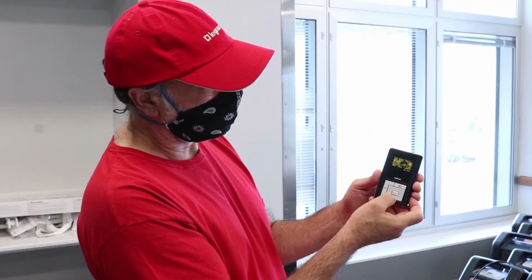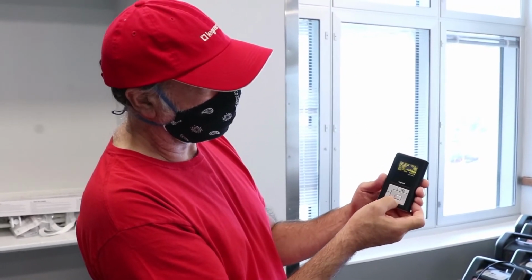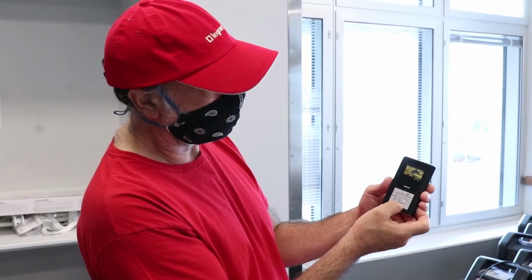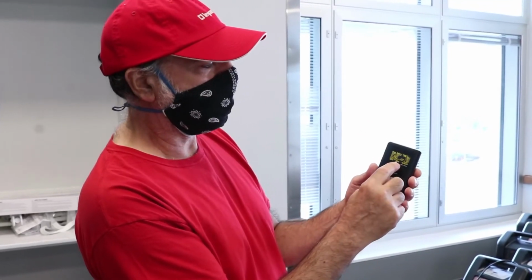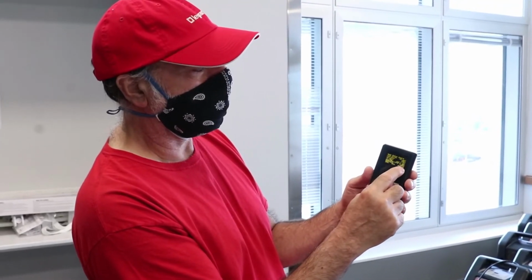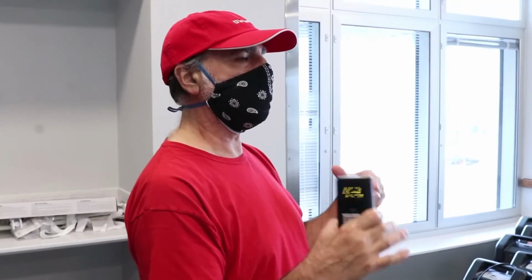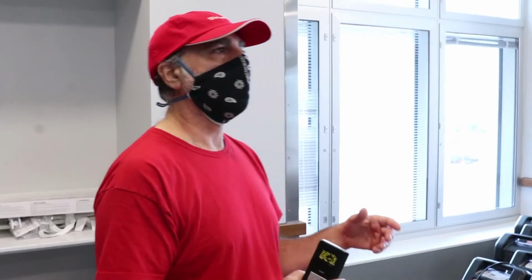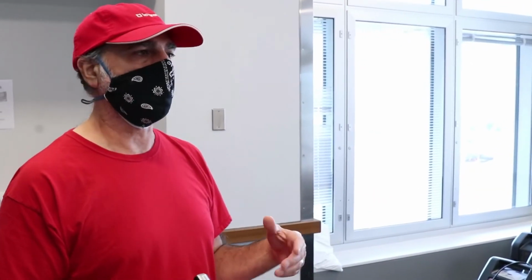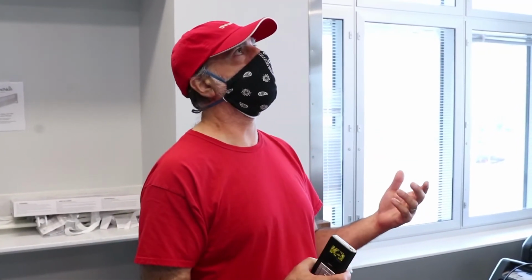The other one down you may consider is retrigger. And what that says is PIR or ultrasonic. What that just means is once you've turned the lights on in the room, it only needs to see one or the other. It doesn't need to see both ultrasonic triggering and infrared, just one or the other.